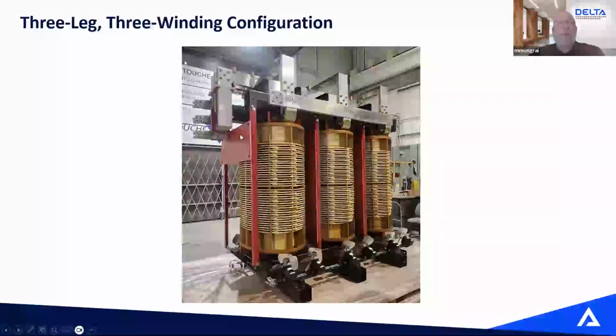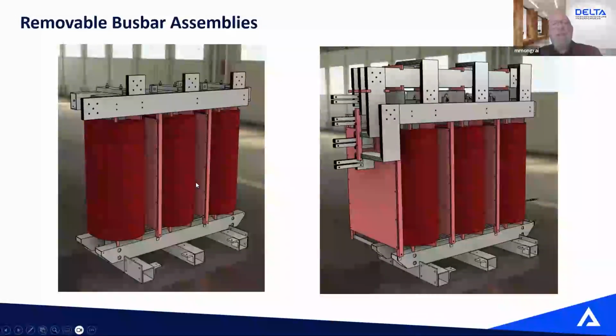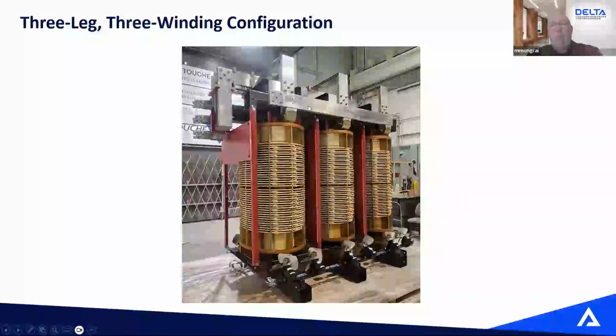So this is a typical three-leg, three-winding transformer. Phase A, B, C, all of your low voltage bus work that will connect to the adjacent or existing low voltage switchgear, complete with fans. So this is a typical unit. One thing that we do at Delta differently is that all of that low voltage busing and HV busing can be easily disassembled from the transformer. All of that low voltage rack is one piece of solid bus bar mounted with solid plastic bus, all fully assembled on a big C channel that bolts on top of the core and coil.